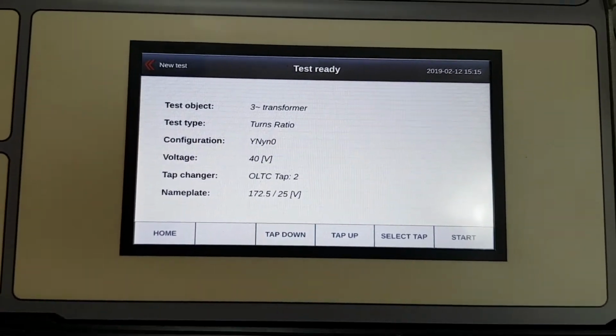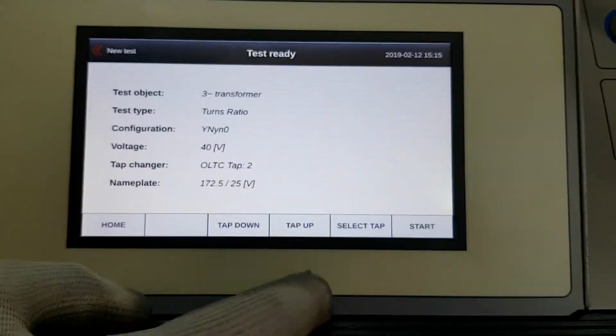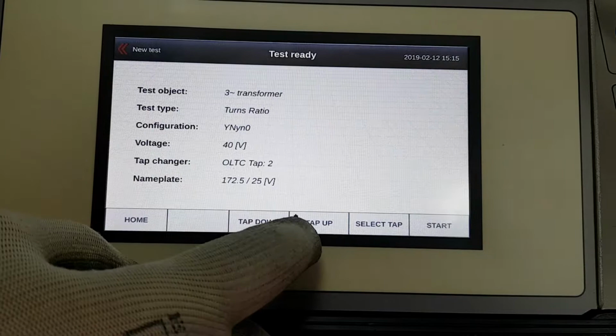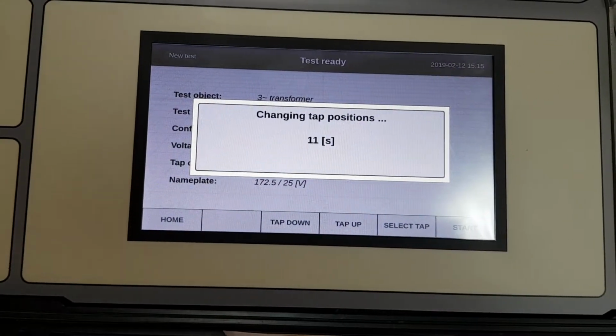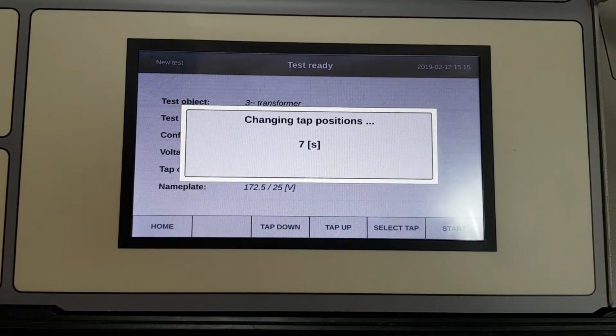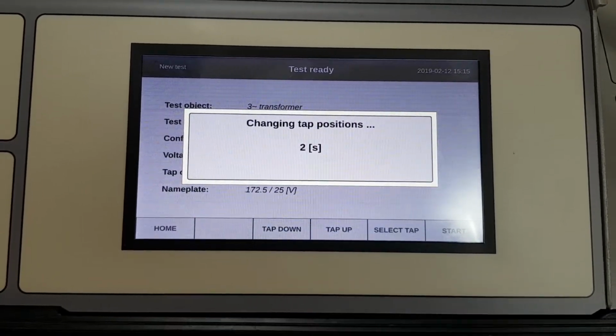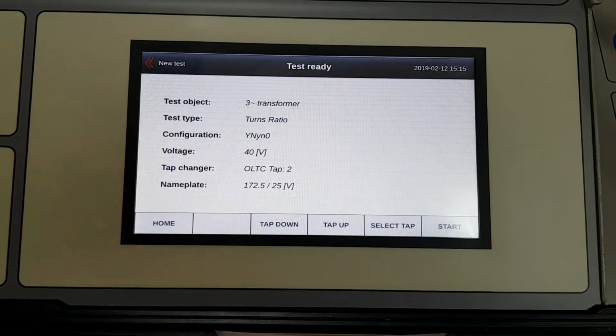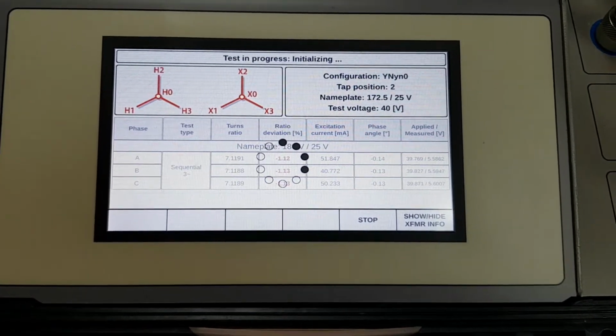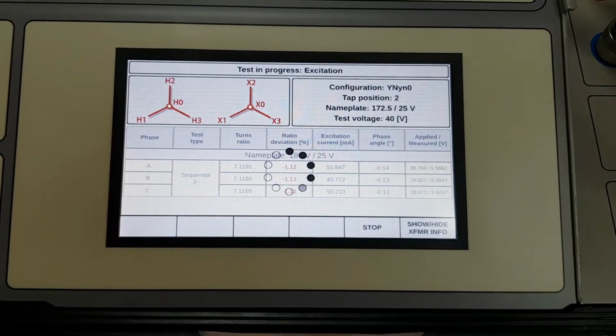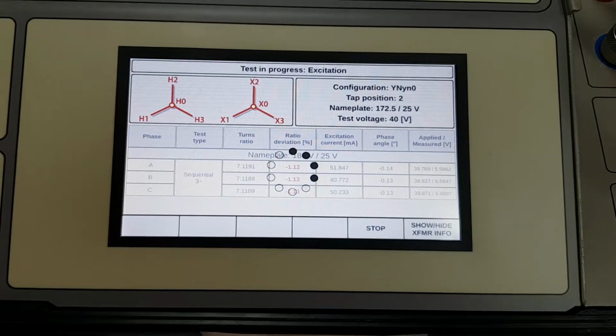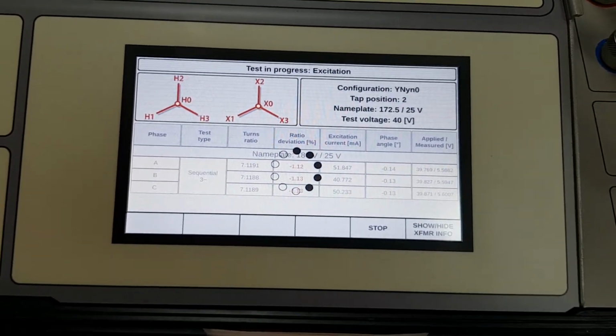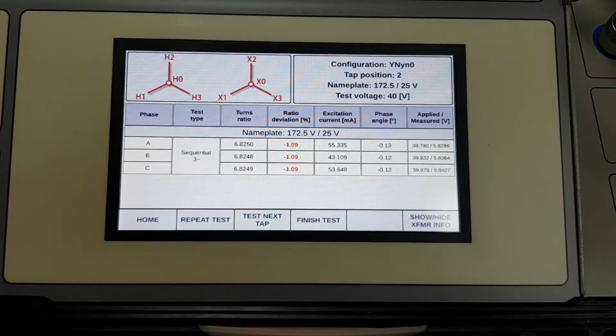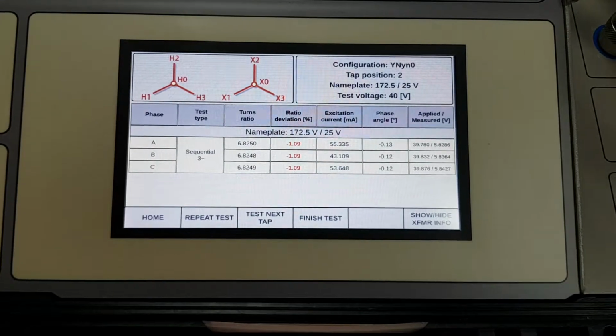So it shows the test ready screen for the next step. We can remotely change the tap position using the built-in tap changer control unit. So if I click the tap up button, it will remotely change the tap position of our on-load tap changer. And once the tap is changed, I can start the test in the second tap position. Now we have results in second tap position.